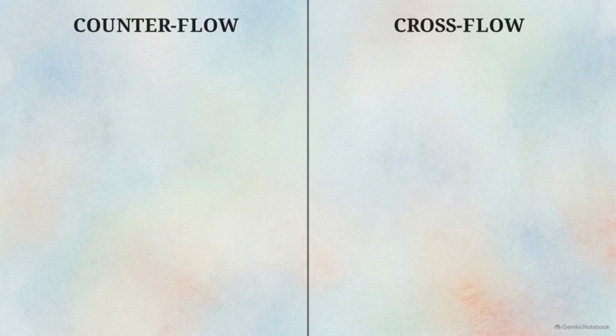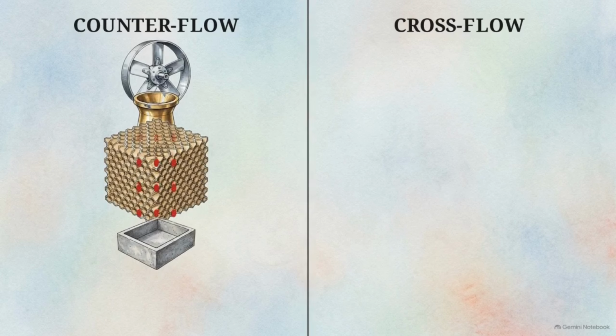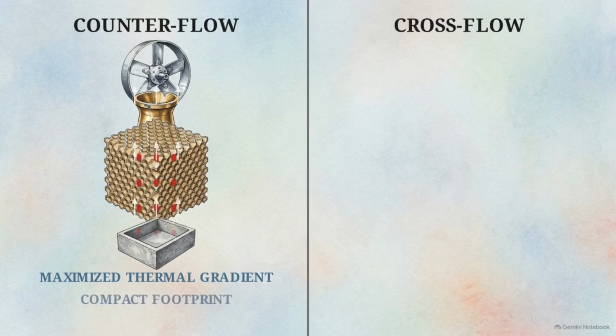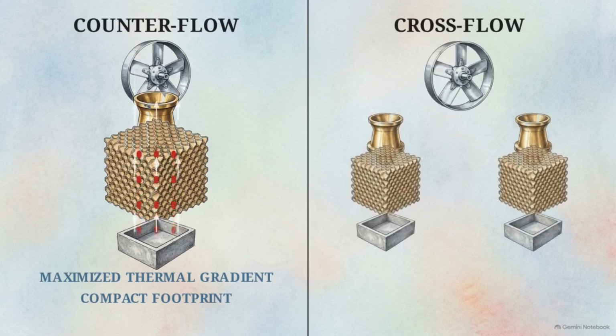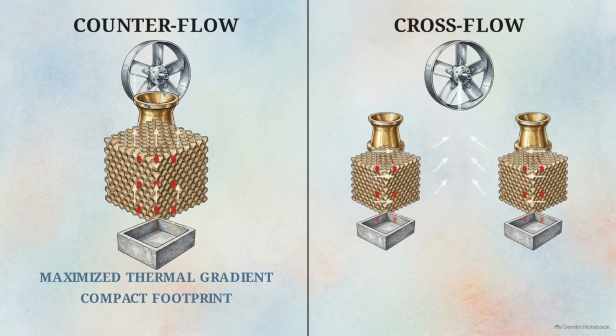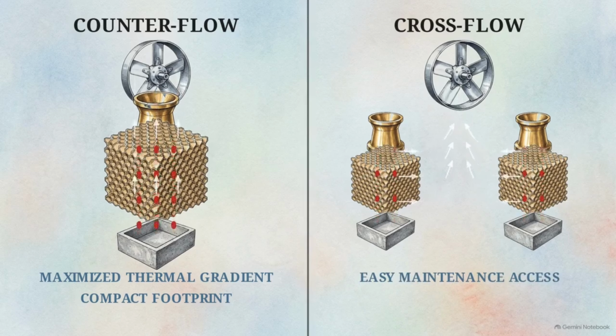Returning to commercial mechanical draft units, engineers must select between two primary internal airflow architectures. In a counterflow configuration, water falls strictly down, while air is pulled strictly up. Moving the fluids in exact opposition maximizes the thermal gradient and creates a highly compact footprint. In a crossflow tower, water still falls vertically, but the air is pulled horizontally across it. This geometry generally simplifies access for routine maintenance.